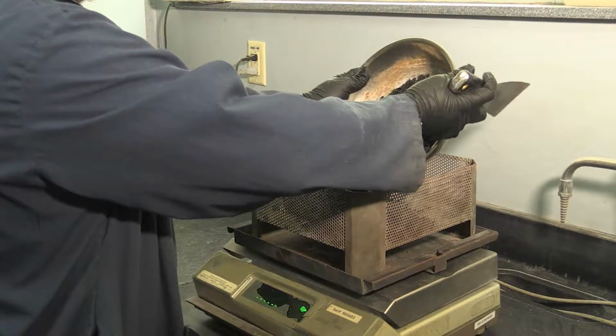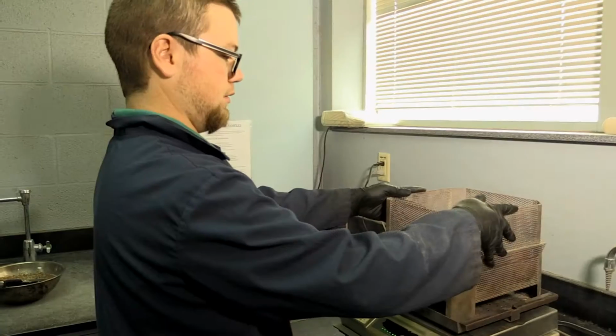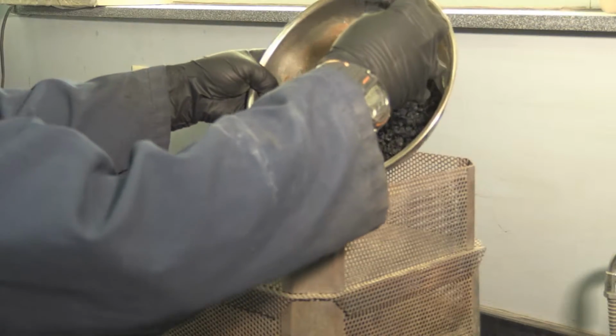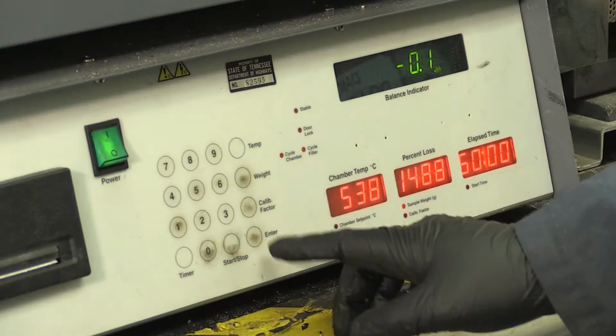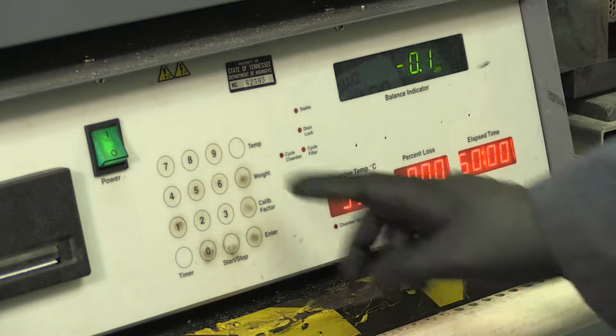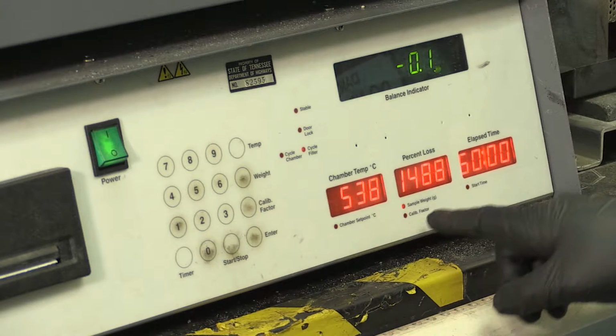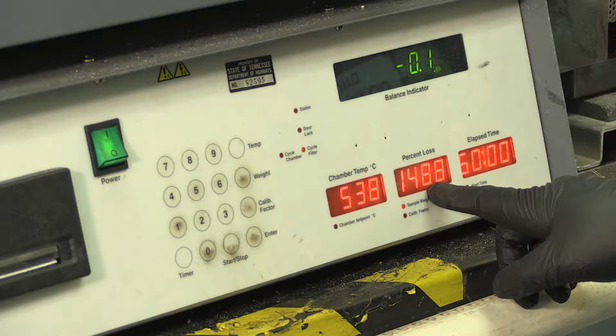Evenly distribute the sample across the basket. If the basket has 2 layers, split the sample evenly between them. Prepare the oven by entering the sample mass and ensuring the calibration factor starts at 0.